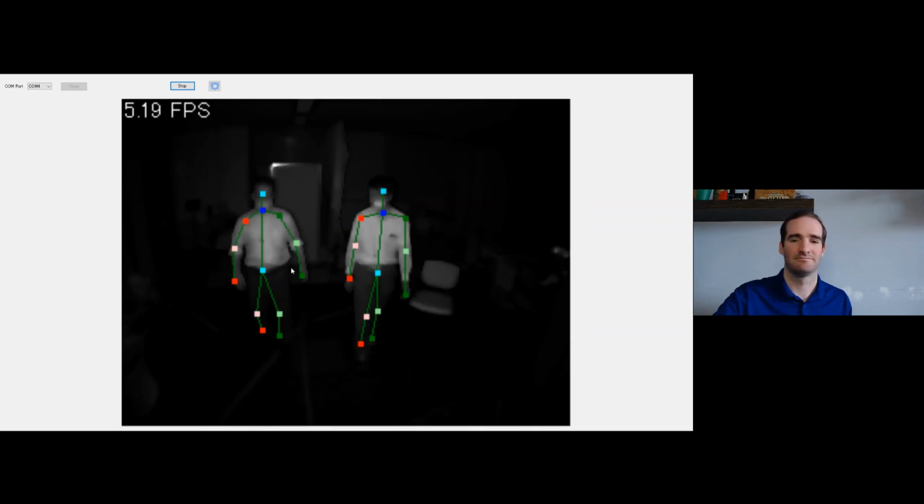Great. Another question that's come in is talking about lighting. Is the sensor performance influenced by ambient light or bright sunlight, different levels of lighting across different rooms? So great question. And no, it is not. We have the sensors capable of running in up to 100,000 lux. That's about the volume of direct sunlight. So the sensor is able to work in there, as well as complete pitch darkness. So it's still able to capture that data effectively without being influenced by any different ambient light.